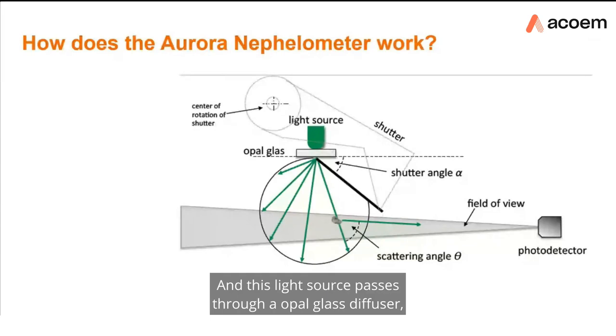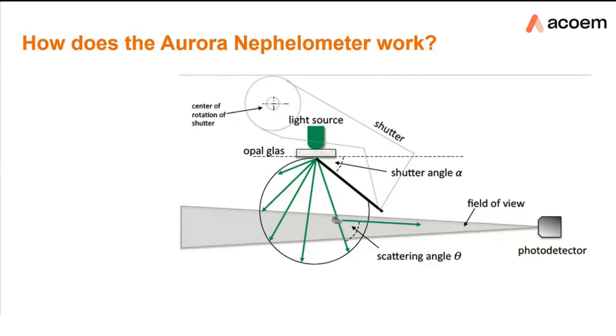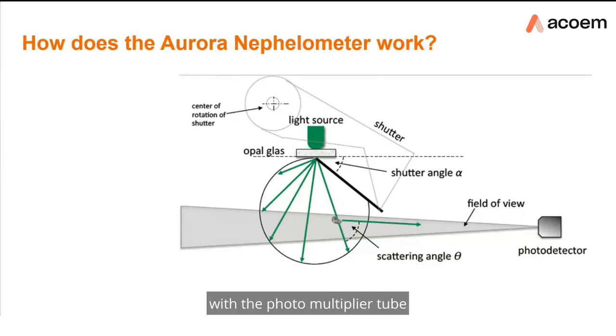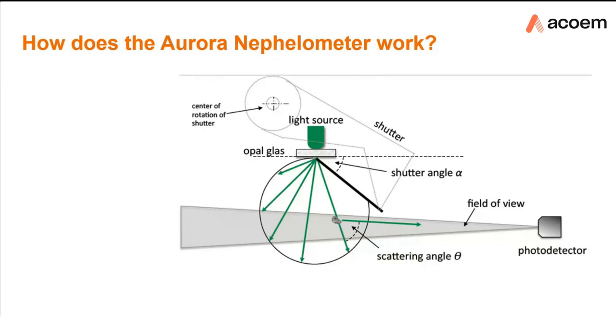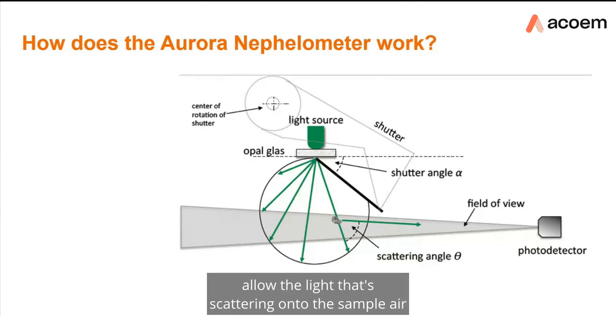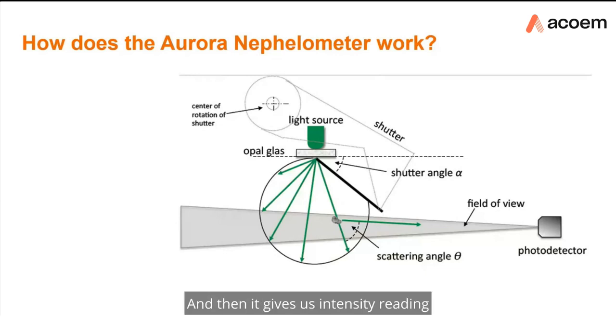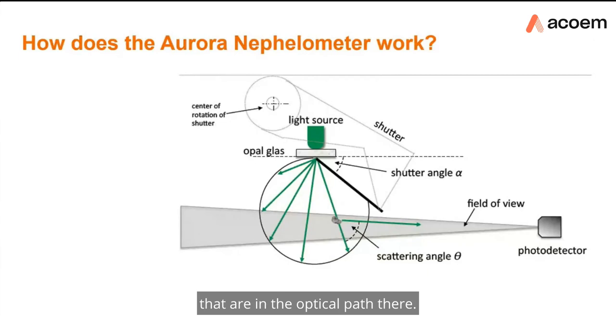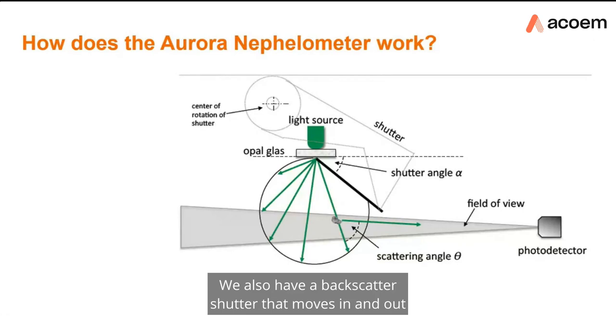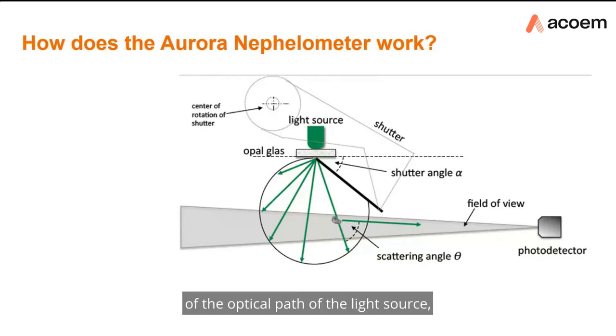The light source passes through an opal glass diffuser which gives its unique Lambertian distribution. The arrangement of the light source with the photomultiplier tube allows the light scattering onto the sample air to be detected, giving an intensity reading in relation to the amount of particulates in the optical path. There is also a backscatter shutter that moves in and out of the optical path, changing the integration angle of the nephelometer.